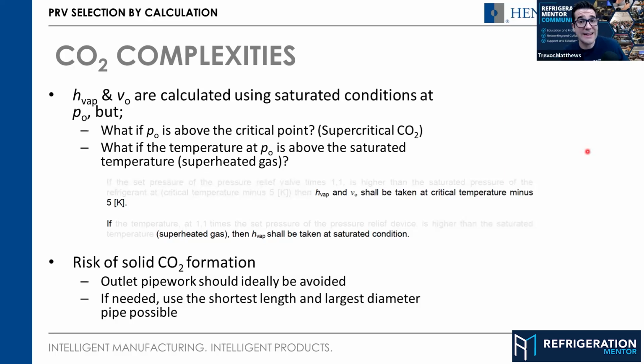You can't have them at the outlet, just like Jordan just said. You can't put a shutoff at the outlet. It's the same thing. If you shut it, even though the pressure relief goes off, it's blocked. It can't go anywhere. And this one here, I talk with designers, I talk with engineers, and I talk with contractors, and it's a gray area depending on where you're at. The best thing possible is to, like Jordan said, not have anything on the outlet and have it be outside, but that's not the case. There's so many pressure reliefs on systems now.